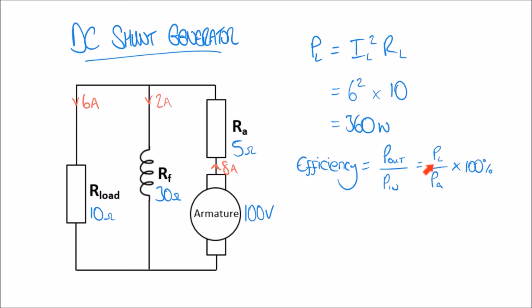We know PL but we need to calculate the armature power first, using the formula P equals I times V. We use the armature current and the original voltage produced at the armature: Ia is 8 amps and the armature voltage is 100 volts, so the input power is 800 watts.